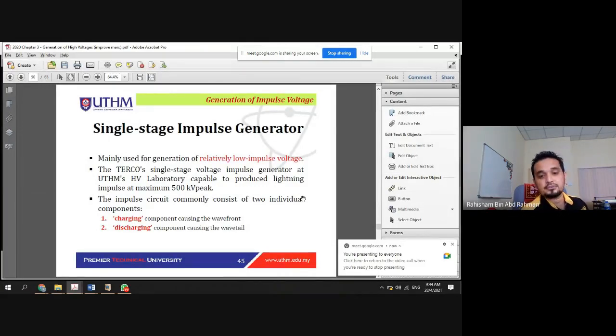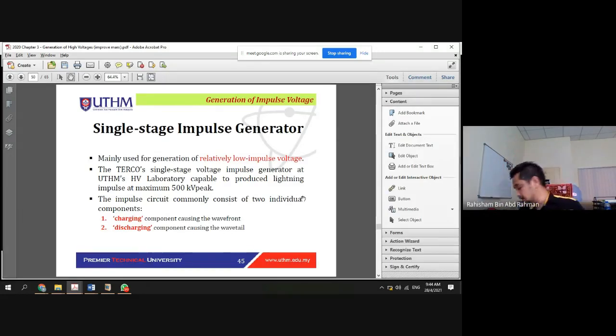What is wavefront and wavetail? These are the waveforms of the impulse. The wavefront is the waveform going from zero to the peak, and the wavetail is from the peak decaying down to zero. That decaying is during the discharge, and the rising part we call charging.